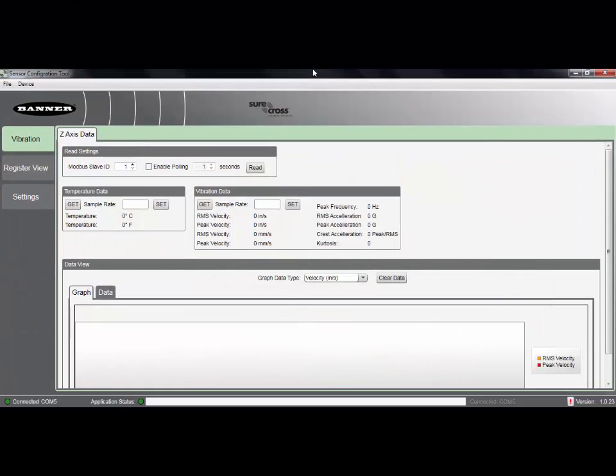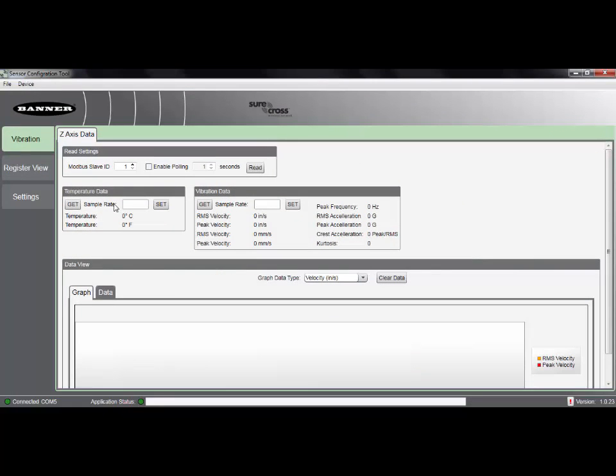When we open up the software, we'll see that we have the ability to change our sampling intervals for the vibration sensor. Currently my sensor is set up at its default settings of a 16,000 millisecond or a 16 second update for temperature and a 62 millisecond update for our vibration data.